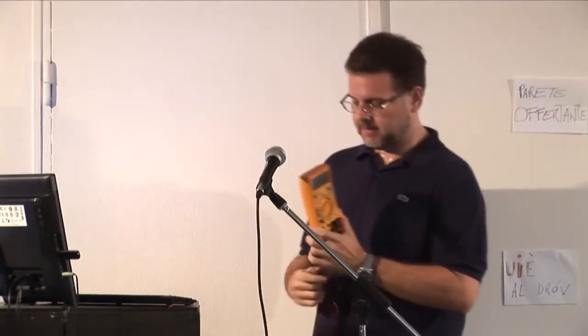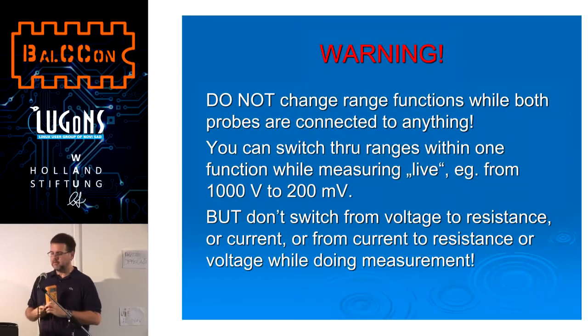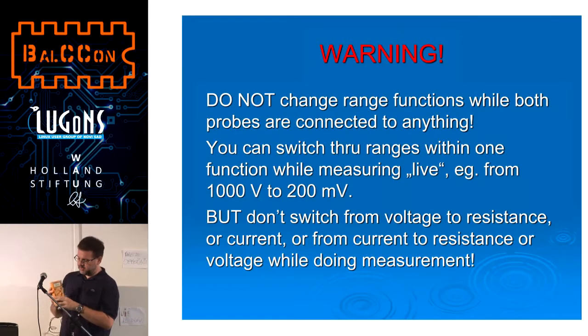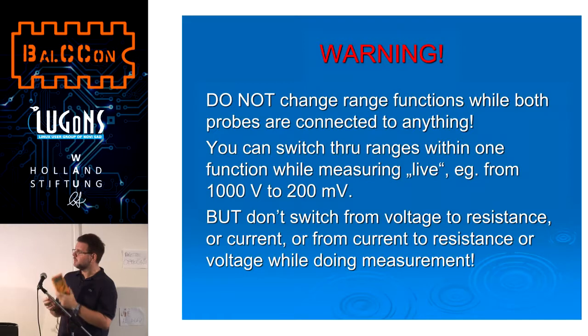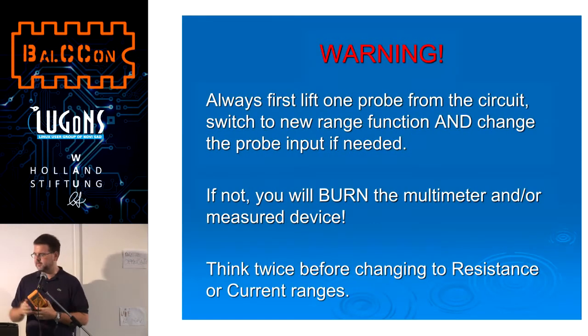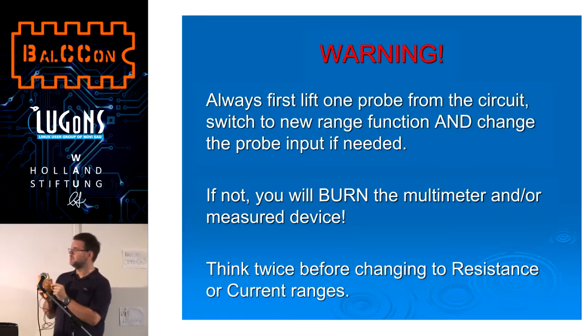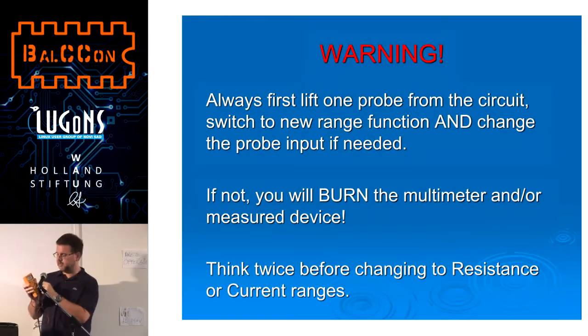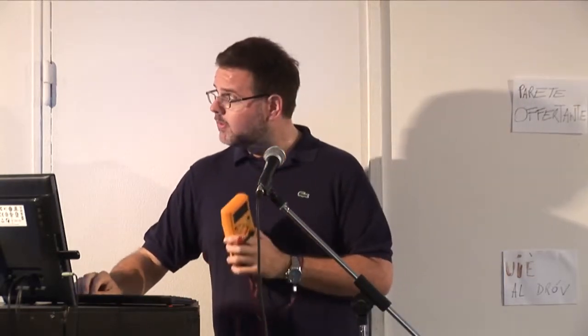If you know what voltage you're going to measure, put your range one step higher. If not, start from 1000 volts. You have to remember: never, never, never change the function while measuring. So if you're measuring voltage and decide to measure resistance, don't leave your probes in — you could burn something, the multimeter or the device you're measuring. Always lift one probe when you change functions. You can change voltage ranges during measurement, but not from voltage to current to resistance.